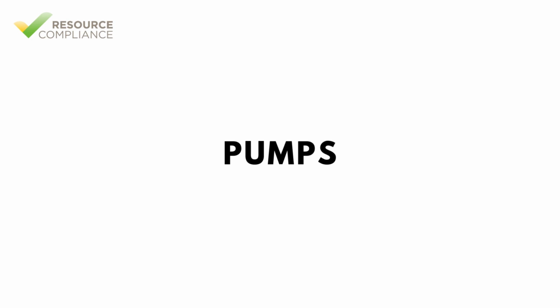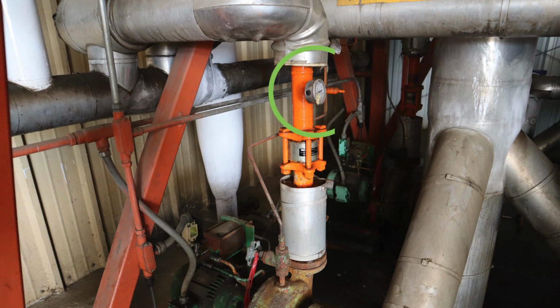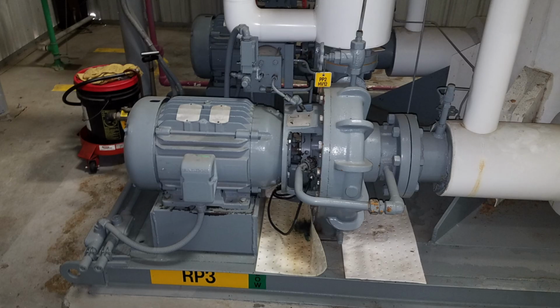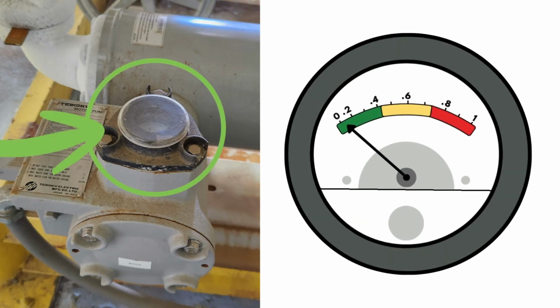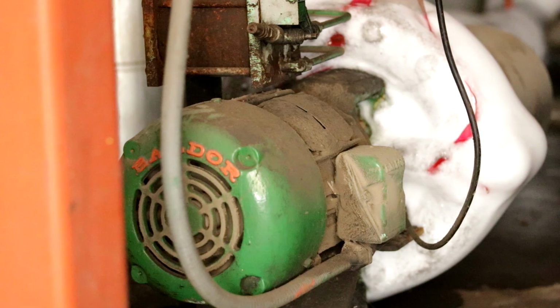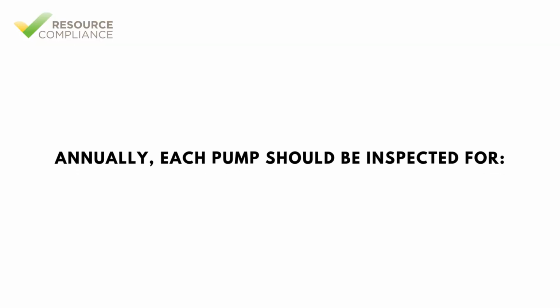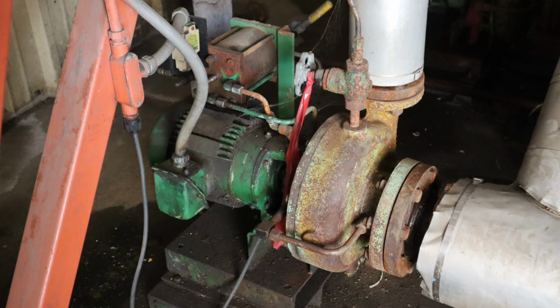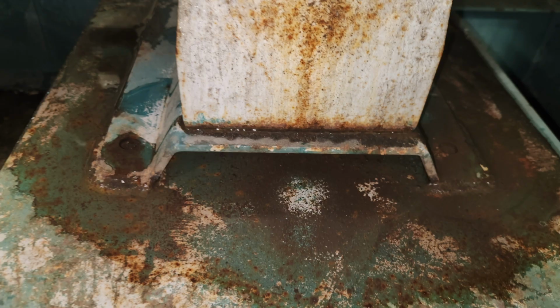Refrigerant pumps should be regularly inspected. At minimum, weekly inspections should ensure that the pump discharge pressure is acceptable, open drive pump shafts are adequately guarded, and the oil level in the reservoir is acceptable. For hermetically sealed pumps, the bearing wear monitor should be in the acceptable range, and the pump should be free from abnormal sounds and vibration. Annually, each pump should be inspected for surface corrosion and pitting and proper anchorage.